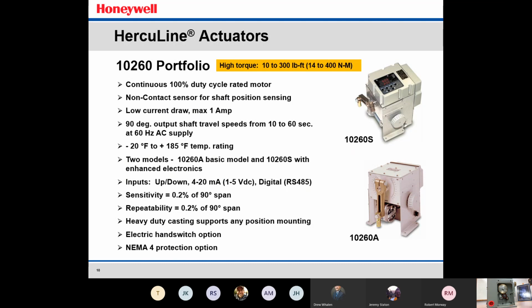The actuator also has a non-contact sensor for shaft positioning. If the customer needs a true indication feedback to the control system, whether it be a PLC or a single loop controller, that shows the actual position of that actuator, the actuator has a non-contact sensor, which is much more accurate and less maintenance headaches out in the field.